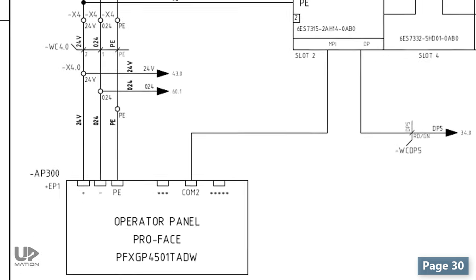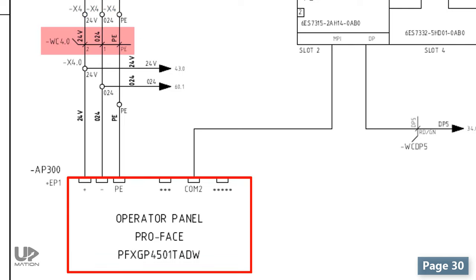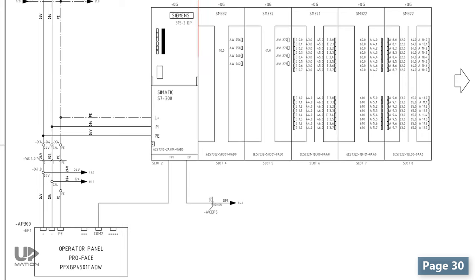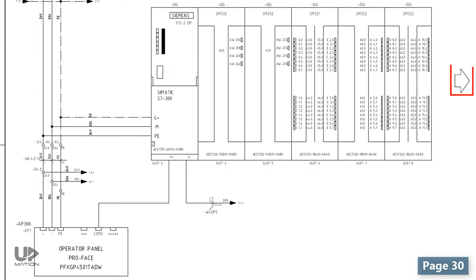On the other hand, the operator panel has been powered up from the X4.0 terminal blocks using a cable with the WC4.0 tag. This is the standard way to illustrate the cable and its core numbers in a wiring diagram. The other things we observe on this page are PLC cards that are in the same rack as the CPU. This arrow means that the rack will be continued on the next page.